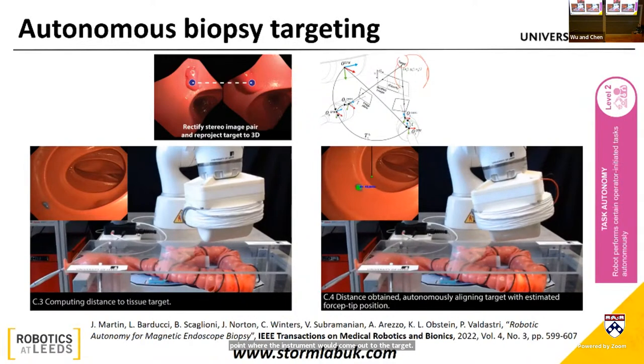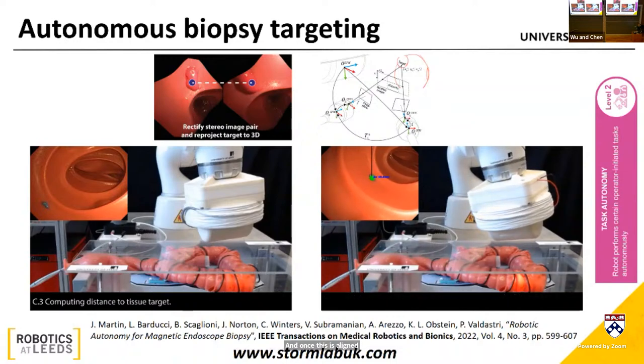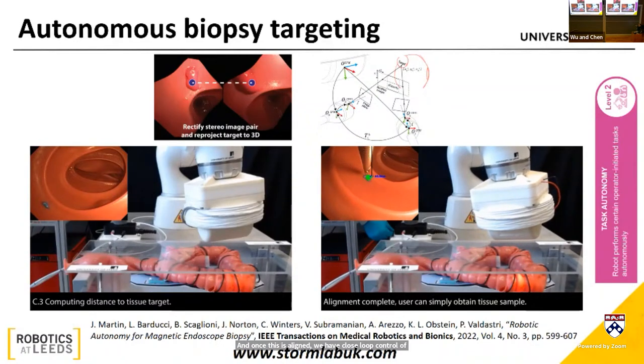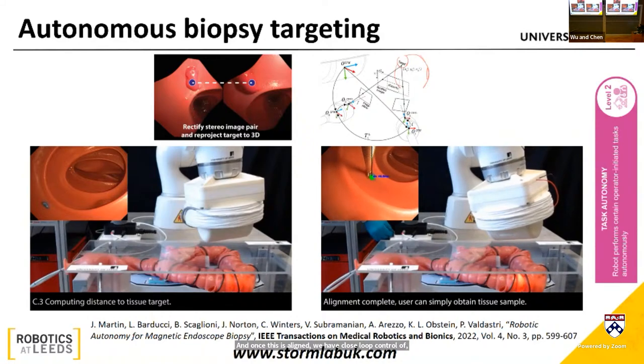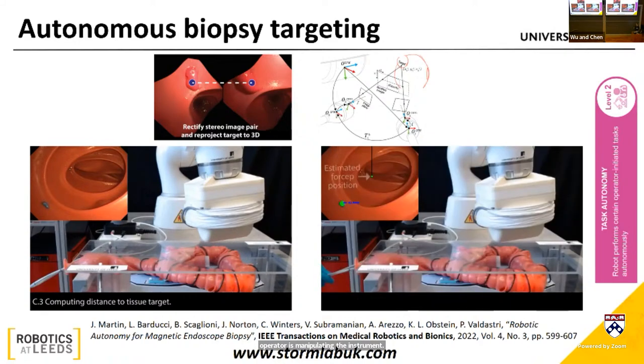Once this is aligned, we have closed loop control of the tip of the endoscope to stabilize while the operator is manipulating the instrument. This is typically a two-person procedure, an endoscopist and a nurse, but it can be done by one single person because the system is basically aiming the tip of the endoscope in a very stable way to get to the target.